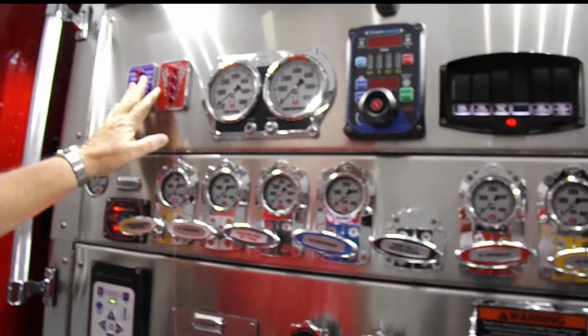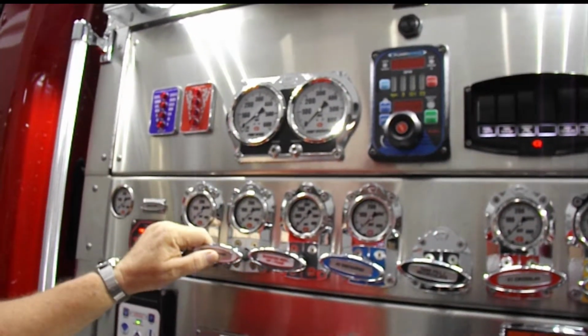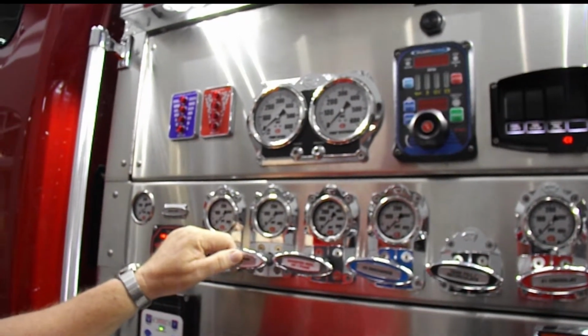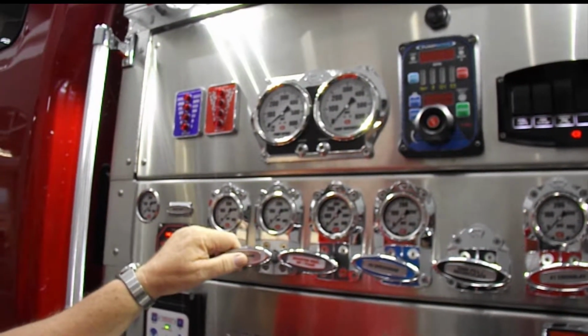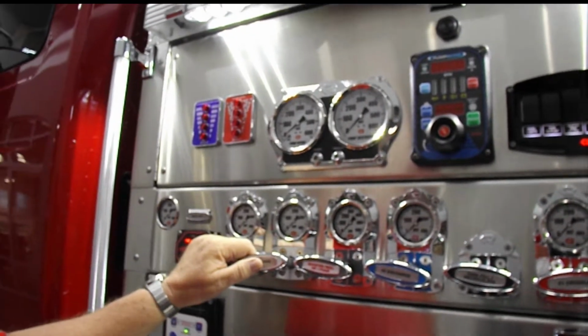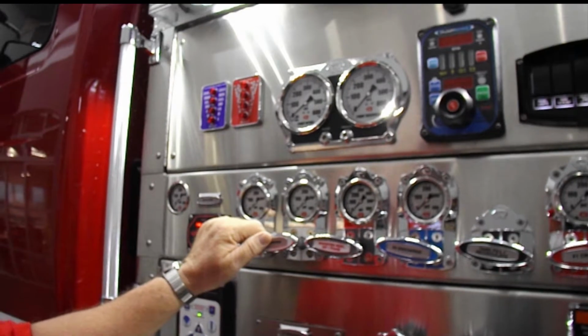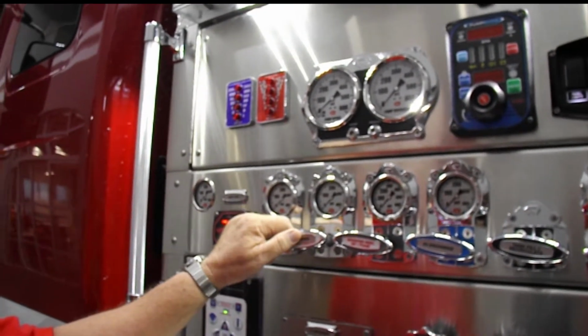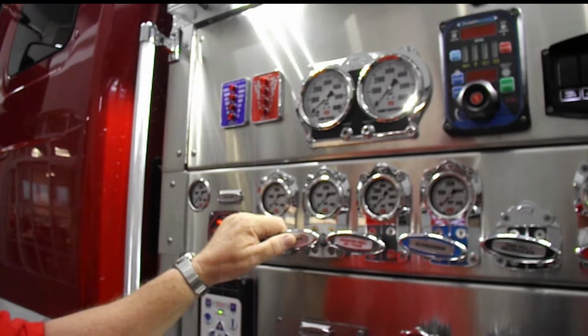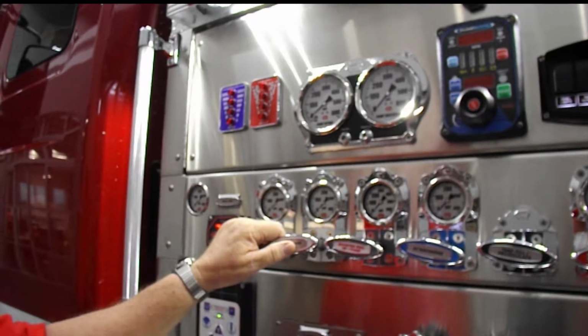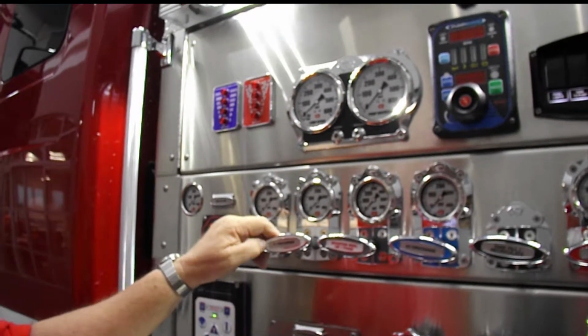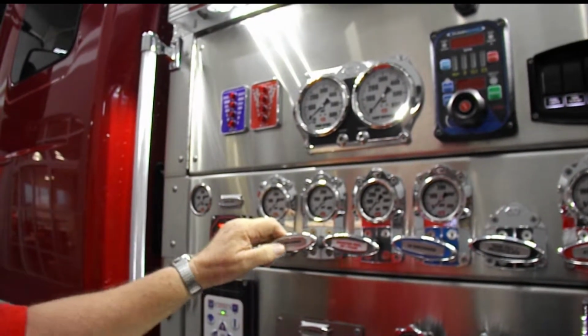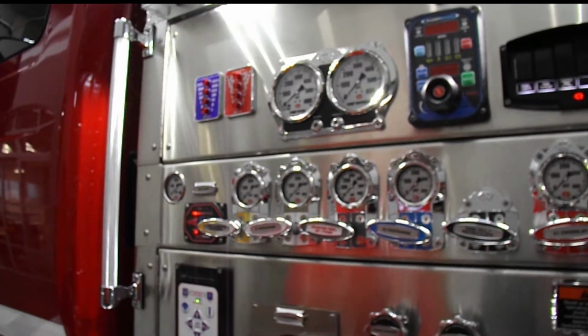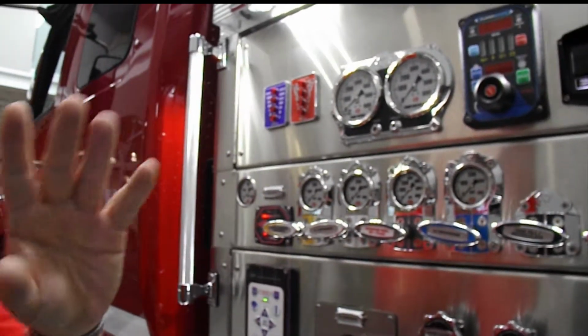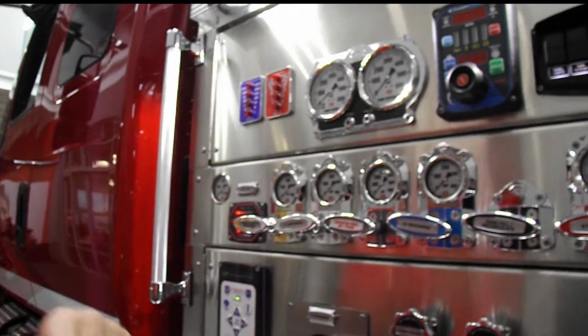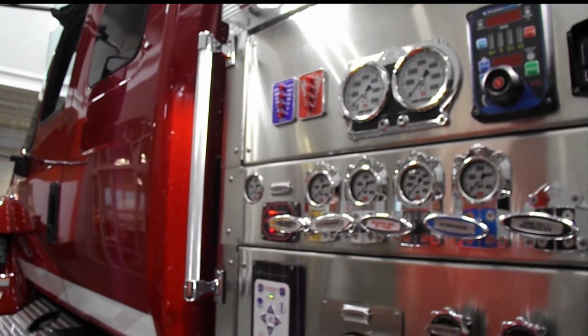Water level and foam level have two separate fills, and they'll both be marked, one water and one foam. It is Class A foam only on this truck, and they're not to be mixed. If you have a big tank car fire and need Class B foam, you can't just dump it in—there is no Class B foam in this system. It's Class A only. If you need B foam, you can pre-mix it in your water tank, or use an inline inductor on the outside, but you can't put it in that tank. You can do it once, and then you'll spend the next week cleaning it out as it gels. It's Class A only.